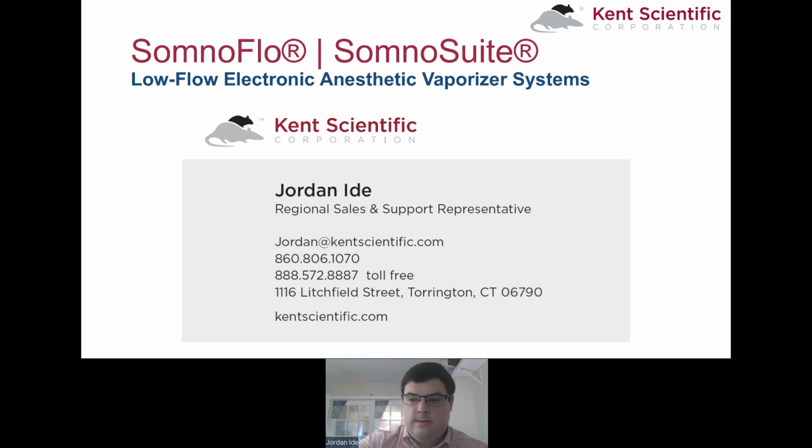Thank you very much. We have another question regarding the Somno Suite syringe. What is the capacity of isoflurane that can be loaded, and how long does that last at max usage for anesthesia? Sure. So we have 2 different syringe options. We have a 5 milliliter syringe and a 10 milliliter syringe.